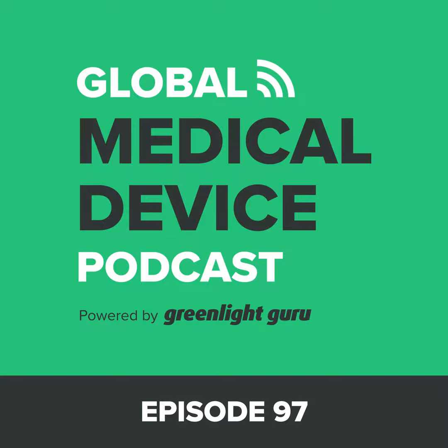We take all of these changes and we package them up into a special 510K. A special 510K has been around for 20 years. The most common reason why we use it is to notify FDA of a change. So we identify the most significant change. We submit it as a special 510K, and embedded in that special 510K, we also include the other changes that we have made, along with all of the supporting documentation, the testing, and so on, to show that the change does not introduce new questions of safety and efficacy. It's not a change in the high-level labeling, the indications, or anything like that.